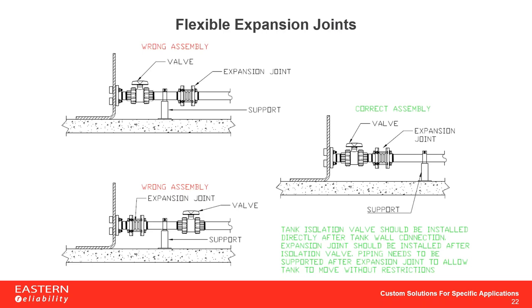Here you'll see the proper ways to install one of the flexible expansion joints. As shown in the diagram, you want the flexible expansion joint to follow any valve in the piping assembly, and after both the valve and expansion joint is where you place the pipe support bracket. This allows the expansion joint to do its job — letting the tank move freely as it empties and fills. This is especially critical on large tanks, as they tend to move considerably more as you empty and fill them.